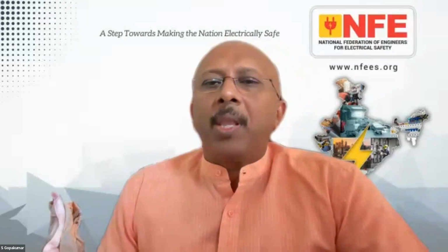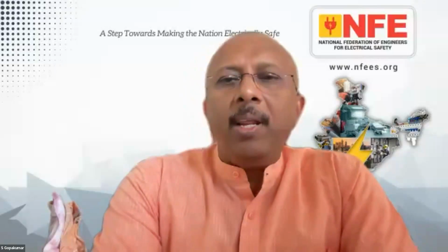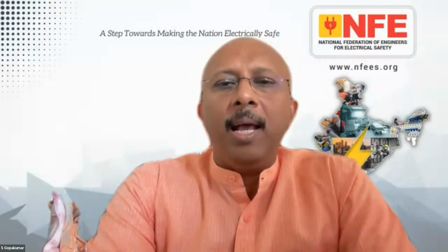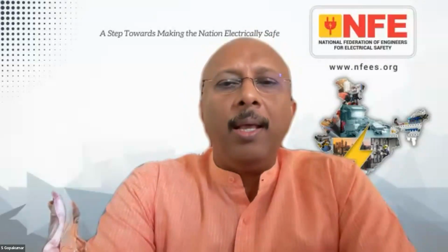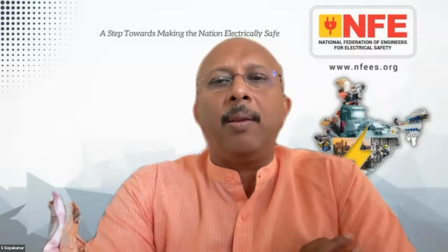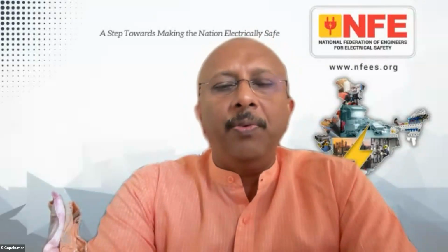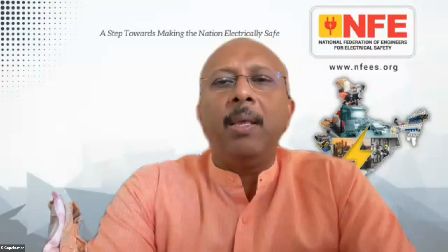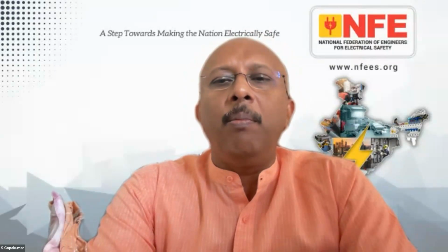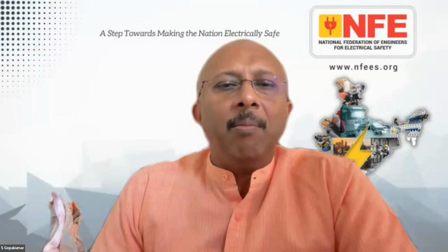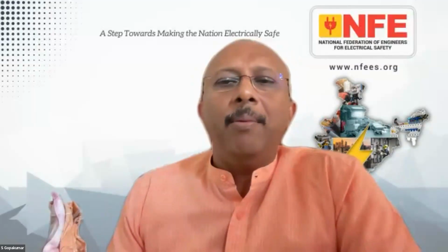Thank you. This is also one of the mistakes that some people in the industry are making, connecting the earth directly to the neutral on the side. This could be dangerous. Of course, after the main distribution board of any building, neutral has to be treated as an insulated conductor. The insulation resistance between the neutral and any other metallic parts of the building must be a minimum of 1 megohm. If the insulation resistance is lesser than 1 megohm, there is some leakage and we are supposed to eliminate that particular leakage.